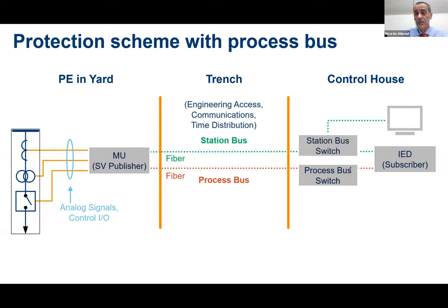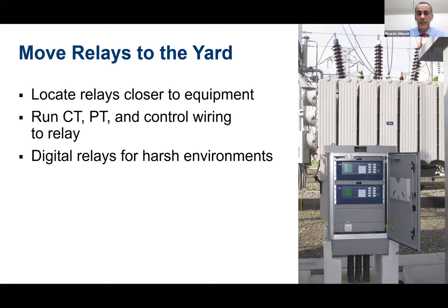We can also connect that merging unit to the station bus, I mean, to the SCADA, okay? To the HMI, to the local HMI in the substation, and also to the remote control center. So we can connect and send information from the breaker status, disconnect switch, and so on, directly. Or another option is not having this connection to the station bus and having only the connection from the IED to the station bus. So the IED will receive the information from the merging unit and will pass that data to the local HMI and to the remote control center. Okay. To apply this approach, we need to have a time sync in the substation, and we can use the Ethernet network that we have in the substation to do that time sync also.